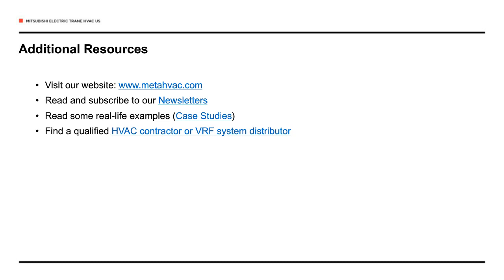Yeah, I'll let Mike respond to the majority of that question, because I know he's up in Ohio and has to deal with a lot of those cold climates, and we talked a little bit about how the low ambient kit works. So Mike, I'll let you explain a little more about that. Yes, the short answer is yes. The long answer would probably take half an hour to explain. Generally speaking, VRF systems can provide full cooling for any indoor unit down to 23 degrees above zero Fahrenheit. And with the low ambient kit, we can take that lower, usually between 0 and -10.